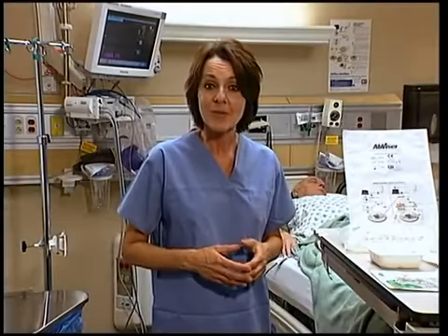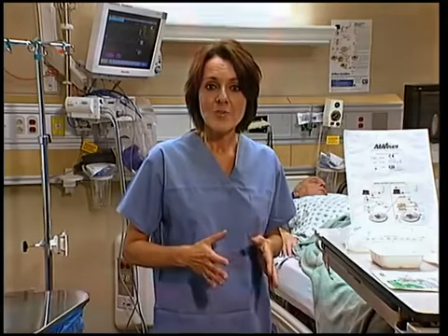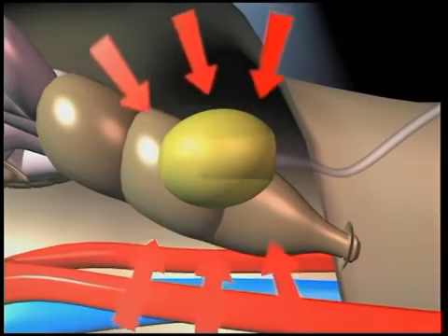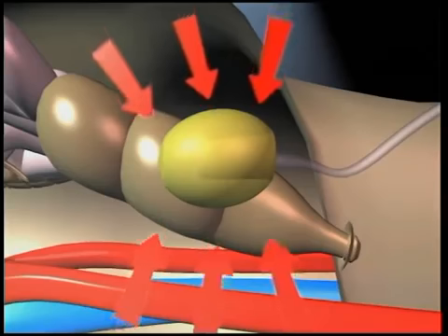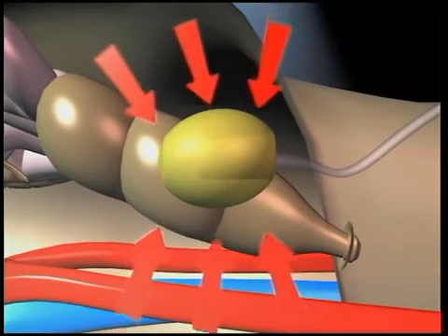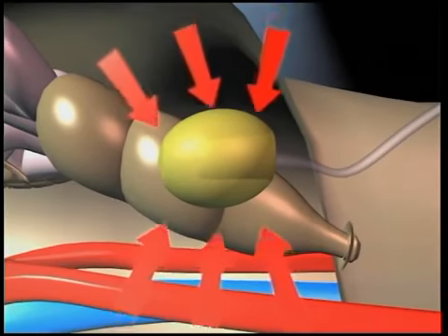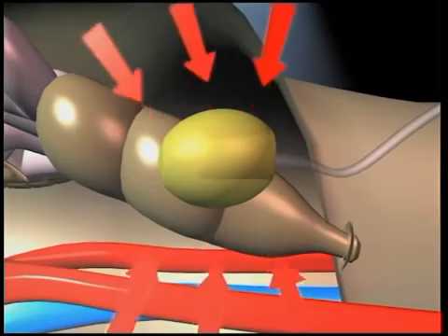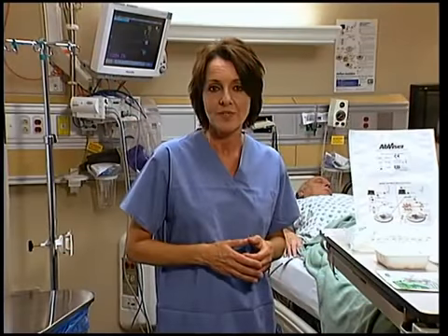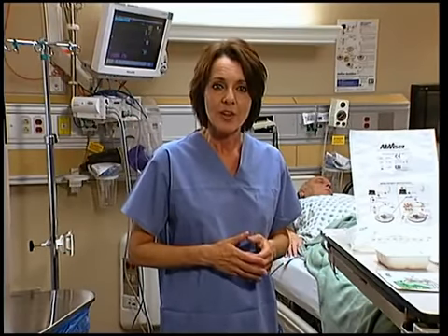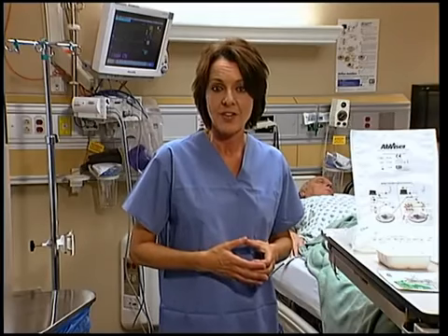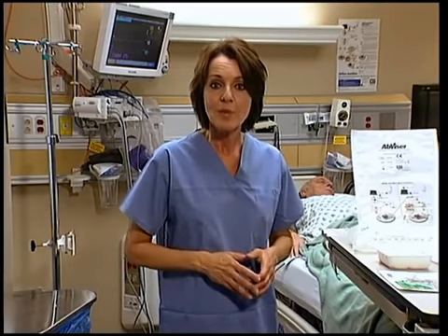Because the bladder is contained within the abdominal cavity, pressure within the bladder directly correlates with pressure in the abdomen. For this reason, bladder pressure measurement through the Foley catheter is now considered the gold standard method for measuring and trending intra-abdominal pressure.